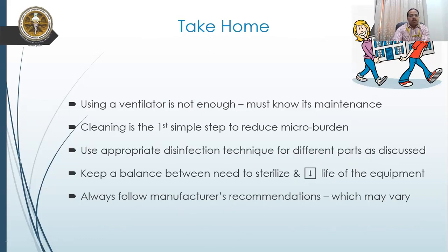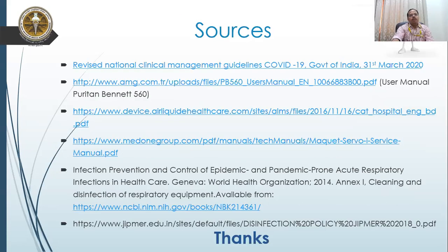So at the end, the take home is, using a ventilator is not enough. You must know how to maintain and how to clean the different parts. The first simple step of disinfection is cleaning itself with plain water, which will reduce the microbial burden or bioburden. Use appropriate disinfection technique as we discussed for different parts of a ventilator. Keep a balance between the need to sterilize and what is happening to the life of the equipment. Always follow manufacturer's recommendations, which may vary from manufacturer to manufacturer.